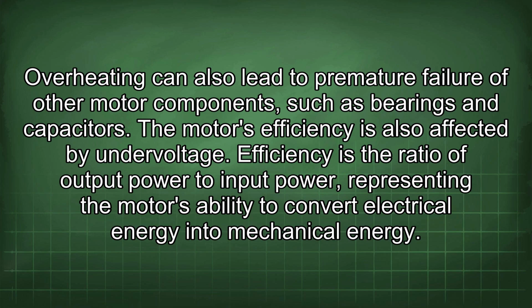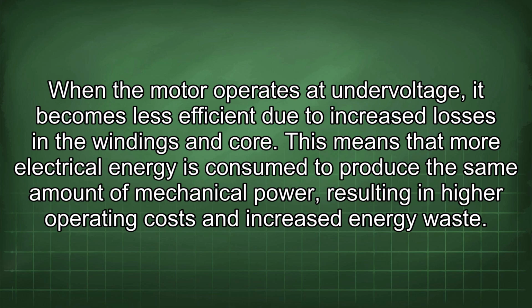The motor's efficiency is also affected by undervoltage. Efficiency is the ratio of output power to input power, representing the motor's ability to convert electrical energy into mechanical energy. When the motor operates at undervoltage, it becomes less efficient due to increased losses in the windings and core. This means that more electrical energy is consumed to produce the same amount of mechanical power, resulting in higher operating costs and increased energy waste.